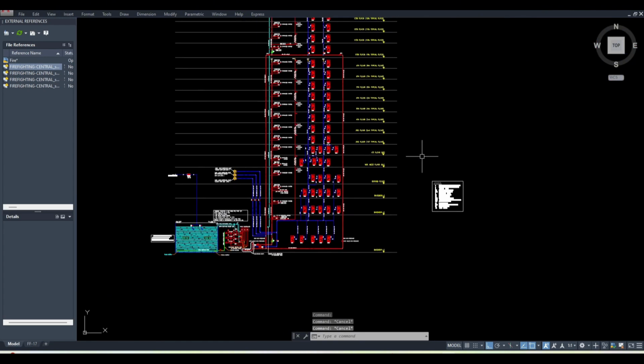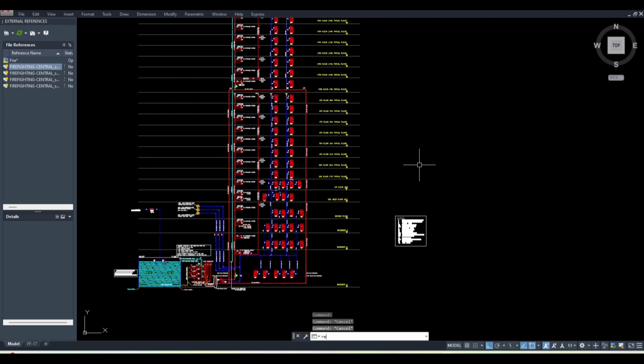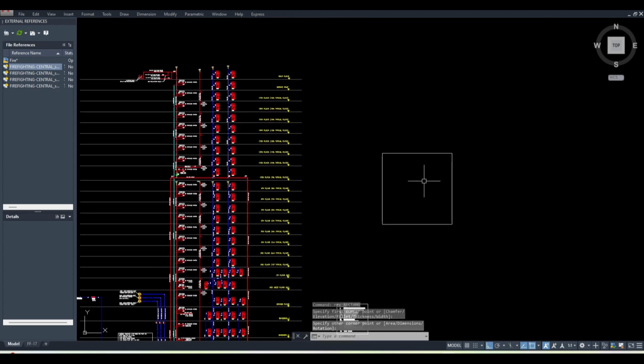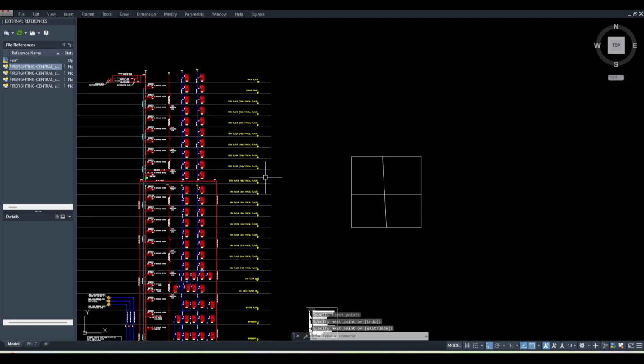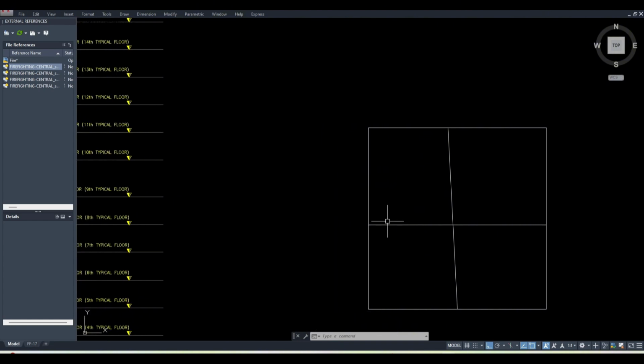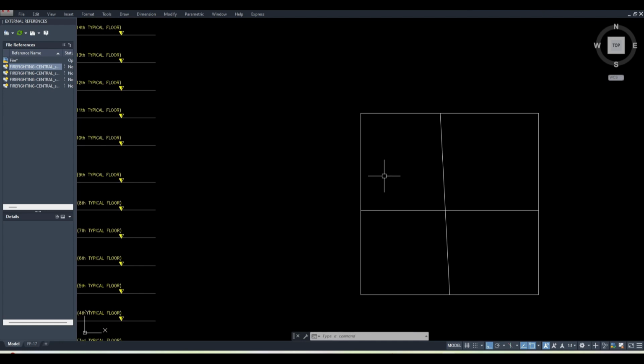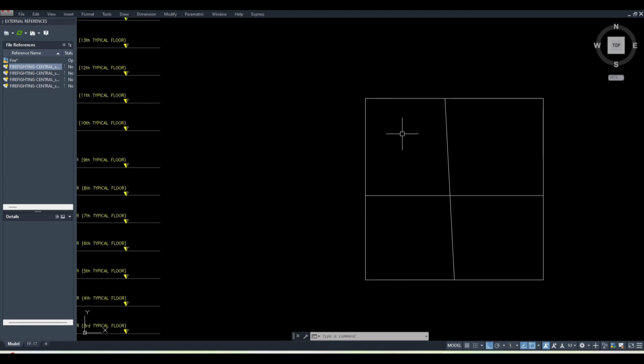Fire zoning means that when the designers design the building, they divide it into zones. For example, suppose this is a building, so they will divide it like this. Of course every floor has to be a separate zone. Also on each floor there should be a zone, and all these zones should be separated by a fire rated wall. It means any fire shall not go from here to here if it occurs here. So this we call a zone.